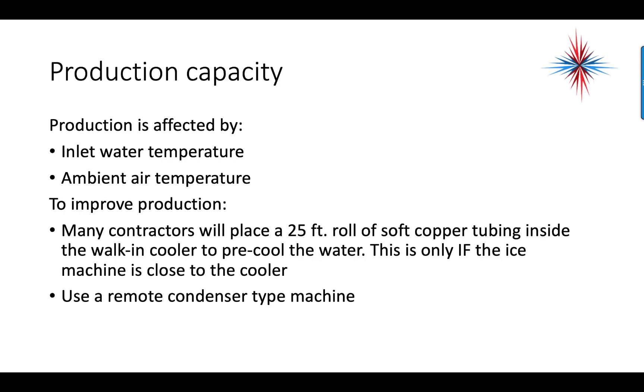Production capacity is affected by inlet water temperature and ambient air temperature. To improve production, some contractors will place a 25-foot roll of copper soft tubing inside a walk-in cooler to pre-cool the water. This is only if the ice machine is close to the cooler. It doesn't work if it's 50 feet away, but a lot of times you're lucky enough and the ice machine sits next to the cooler. You can put a 25-foot roll of pre-cool copper in there.